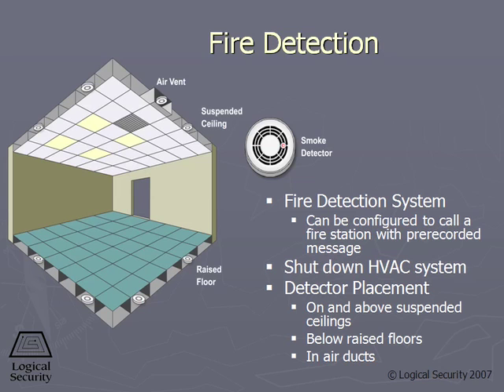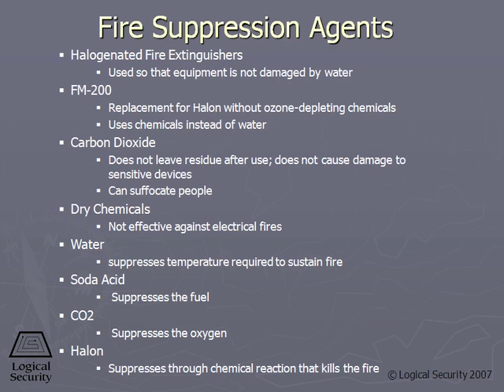Where should we place fire detectors? Approximately everywhere. They should be in the drop-down ceilings, they should be in raised floors, they should be in the ventilation systems, and they should be where we have people. Looking at fire suppression agents, we have gases, we have chemicals, and we have liquids. You'll need to understand the difference between these.